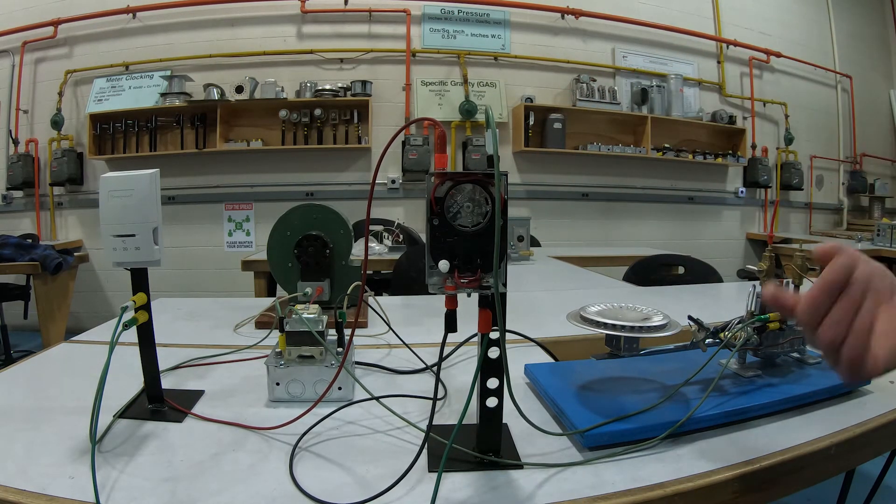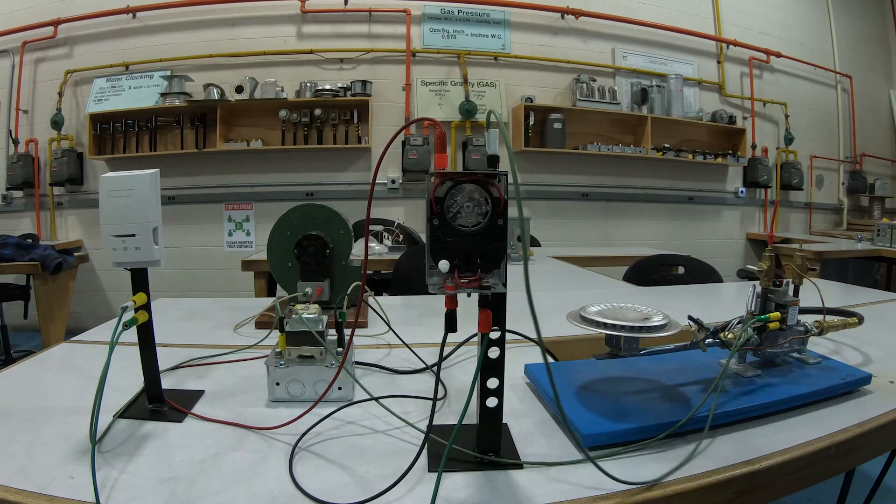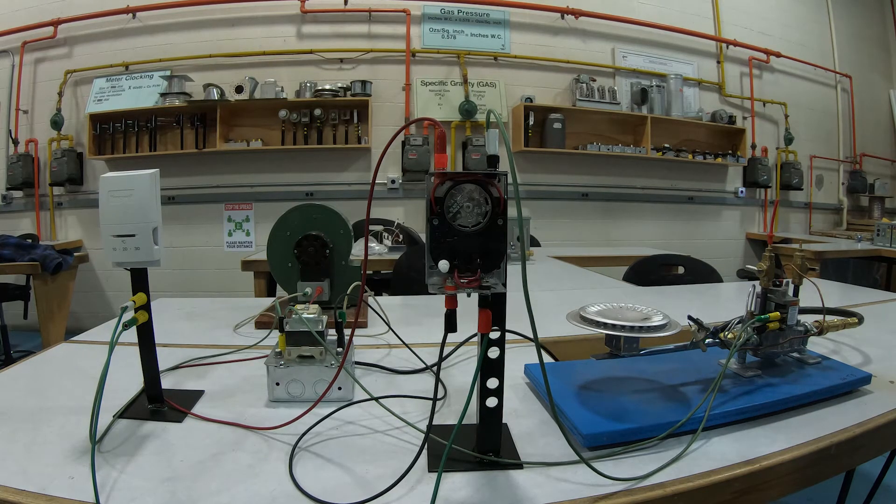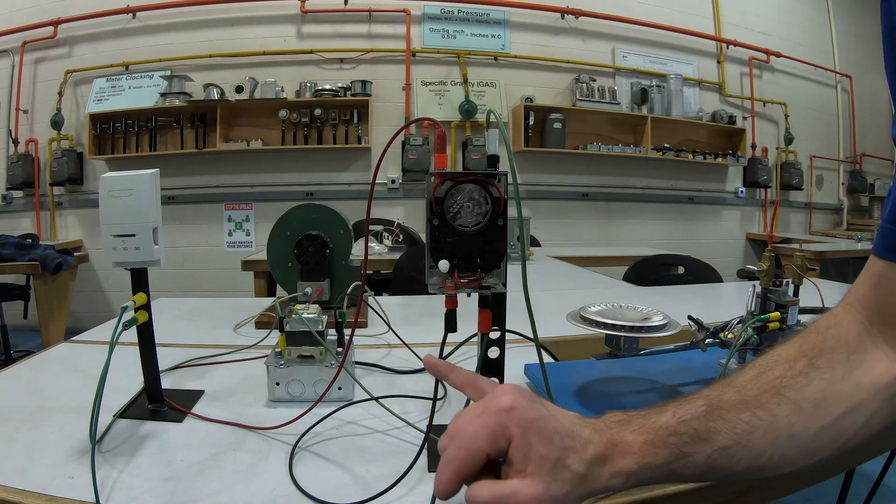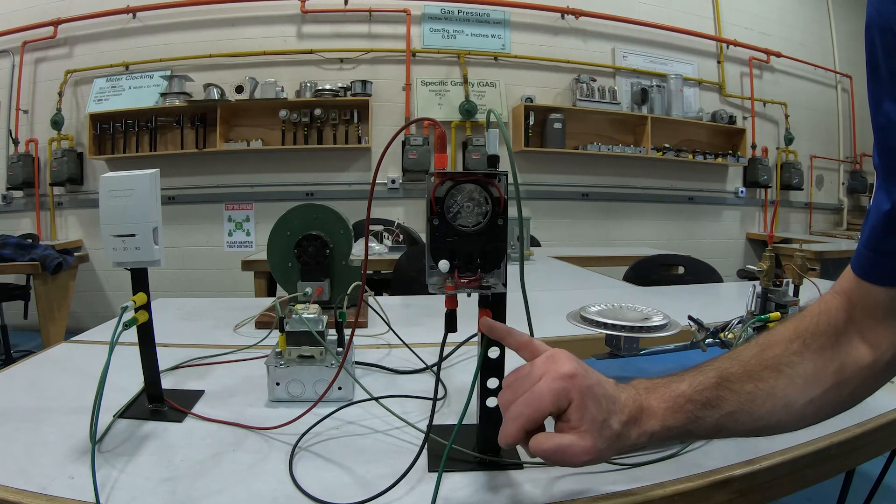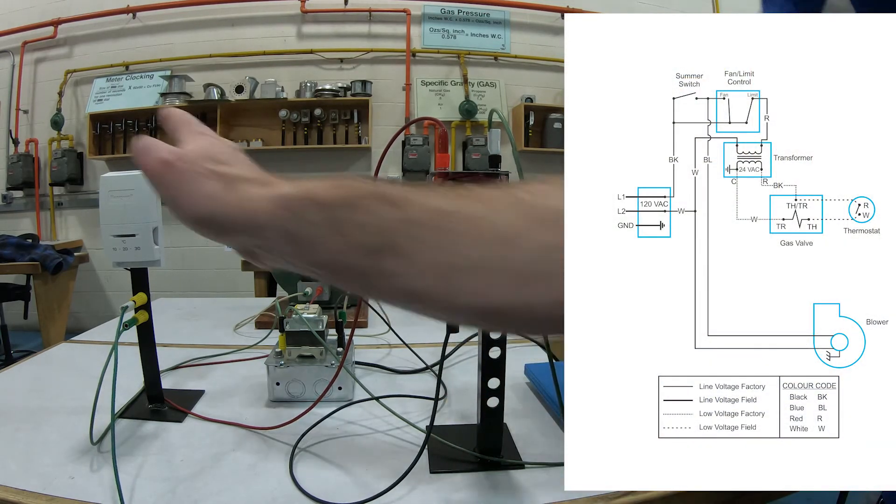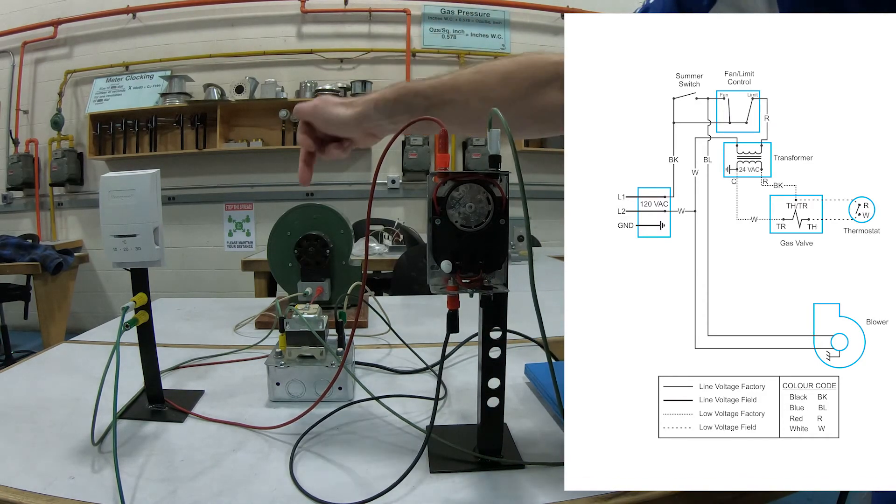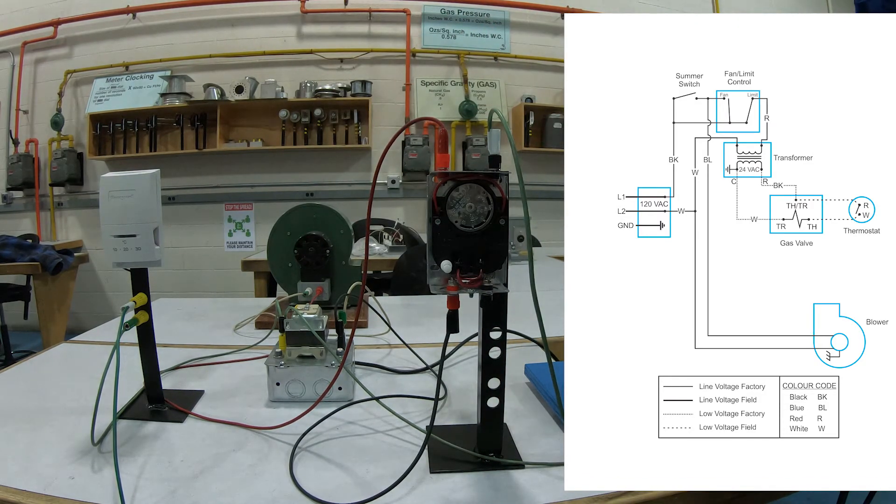So what happens here is when this gets too hot, it interrupts the electricity going to the gas valve, so it shuts off. The other way it could be wired is I could actually have 120 volts going right here, so this would be nothing to do with the thermostat whatsoever. 120 volts comes into here and it goes off to power that transformer. I'm not going to wire that up for you, but that is the other way.